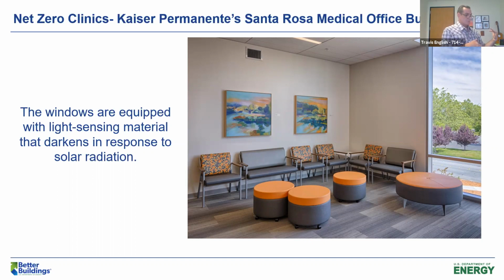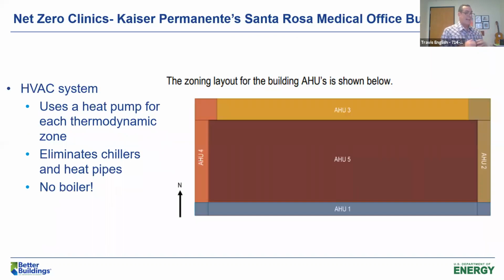In fact, the primary HVAC design strategy is this all-electric system. We have a series of heat pumps, so there's no chillers, and most importantly, no boilers, and no gas line. On this site, being able to eliminate the natural gas and the piped heating system was a $1 million savings to the project. On their budget, they didn't give the $1 million back, they spent it elsewhere, but the HVAC system itself was a savings. So for HVAC we have a north unit, south unit, east unit, west unit, and then a central unit.